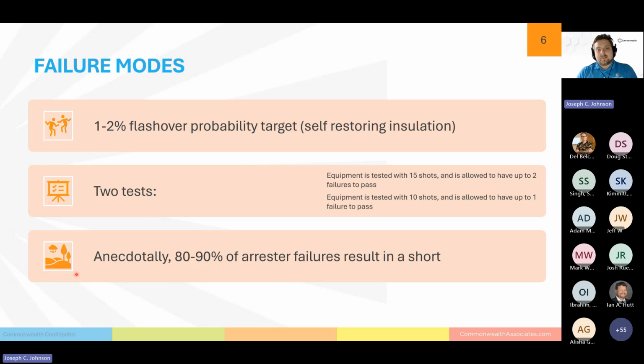Another failure mode is anecdotally about 80 to 90% of arrestor failures result in a short circuit. So if you have a case where your arrestor is beat down, long temporary overvoltage, a lot of lightning strikes, a big switching surge or several in a row, most of the time you're going to fail. It's going to fail into a short, and that's going to effectively look like a fault, and your system won't necessarily be unprotected during those times because you have a broken arrestor, but that arrestor also becomes a fault.